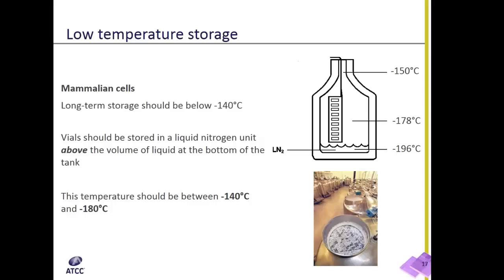Enough liquid should be used to guarantee that the warmest part of the container at the top is always at a temperature at or under minus 140 degrees Celsius. It is highly recommended that vials be stored in the vapor phase rather than the liquid.